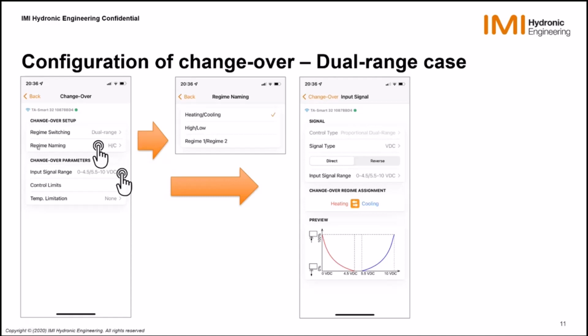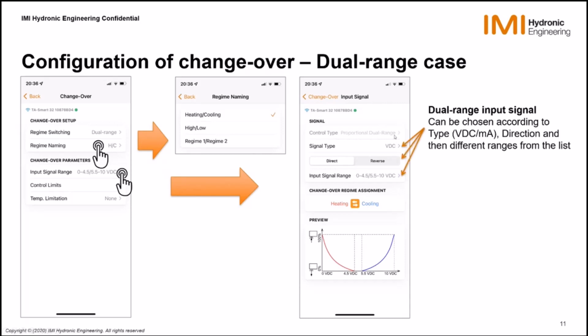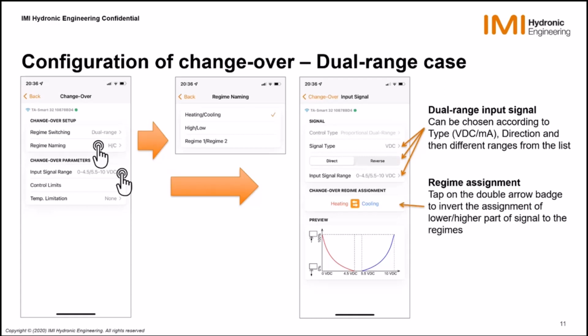I can now go into the first of the parameters, the input signal range. I have, of course, the control limits and the temperature limitation that we will look at later. Input signal range, I come here. As soon as I am in dual range, I will be jumped to the type of control, which is proportional dual range. As before, I can choose my input signal range according to a type, to a direction, direct or reverse, and then amongst the list with and without basically the input line broken detection. Then I have an important one, which is the changeover regime assignment.